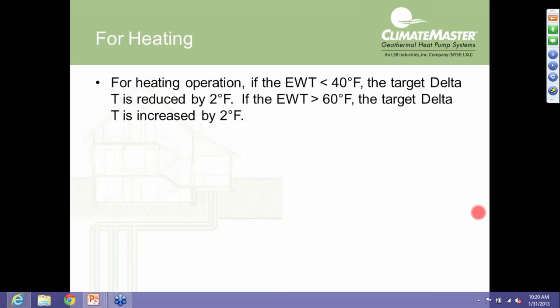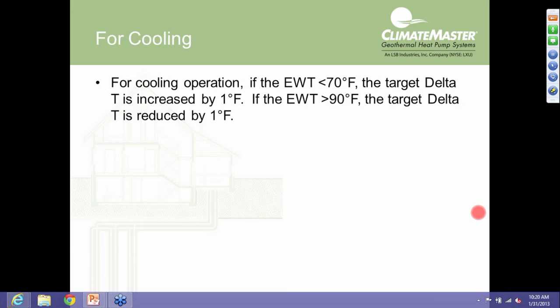The other benefit to that, again, in some of those shoulder times, we are actually, with the hot water generator, able to produce hot water when we were not before by slowing that water flow down through that coaxial heat exchanger, keeping that compressor in a better operating envelope, keeping that discharge temperature back up a little bit, where we can actually make some hot water. Now, on the cooling side, we do much the same thing. If our entering water temperature is less than 70, then we increase it by 1 degree, thereby slowing the pump down. If the entering water temperature is greater than 90, hey, we're starting to get a warm loop here, we reduce it by 1 degree, again, speeding the pump up, increasing the turbulent flow, hopefully a little more heat transfer into the ground.